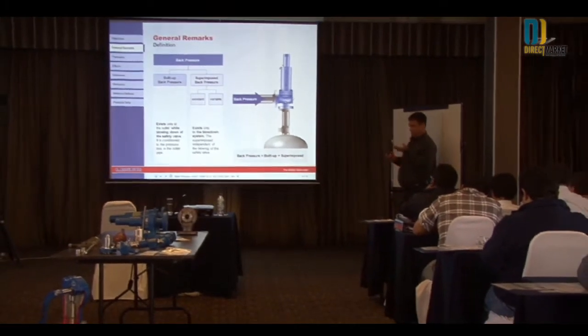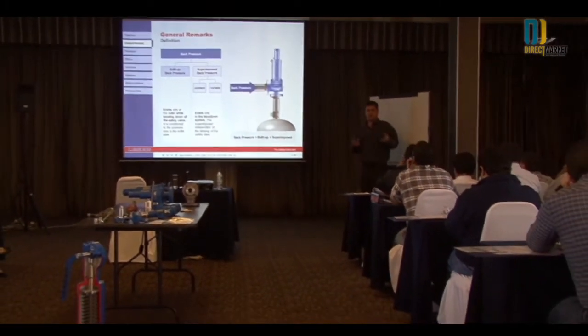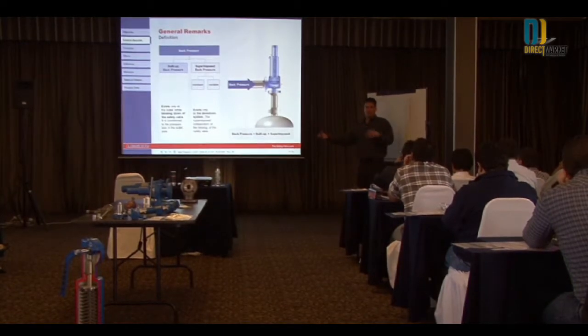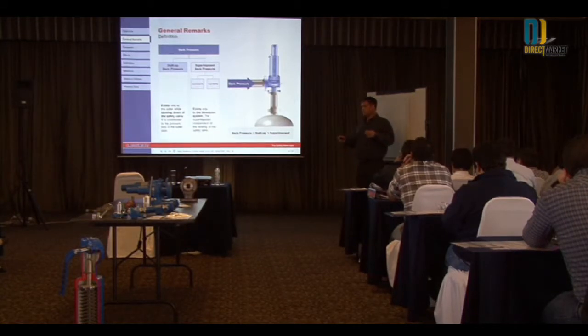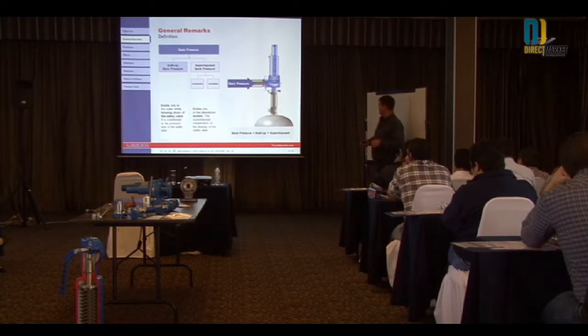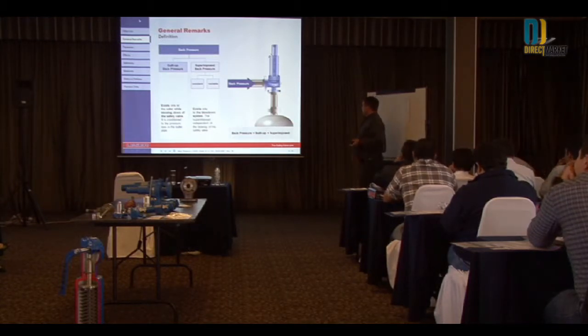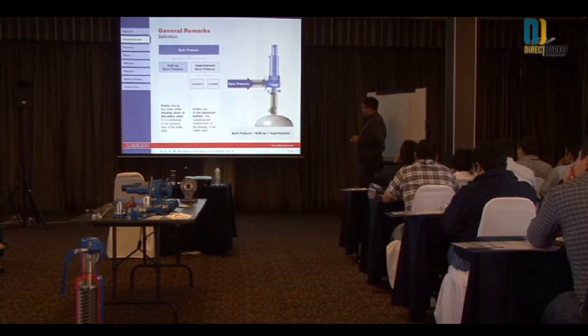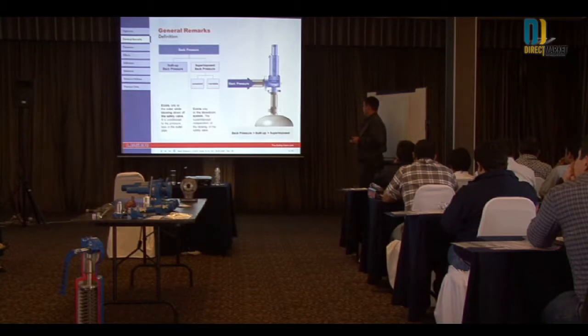Superimposed back pressure can be either constant — for example, if you have your valve outlet piped to a vessel where you're trying to recirculate material, that could create back pressure, or if temperature gets higher and expands. Variable is back pressure that changes. Superimposed back pressure exists independent of the blowdown of the safety valve.